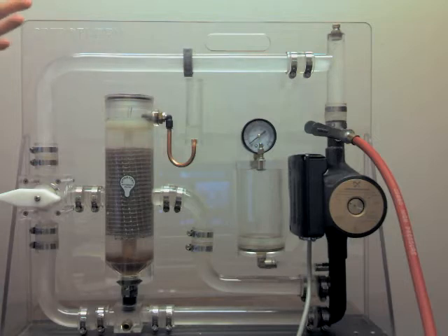What we want to show you here is that I pumped in a lot of air and this system is still circulating right now. So you may think, well, I don't really have any problems with air. My facility is heating or it's cooling fine. Nobody's complaining. The system is working. You still may have air in there, and you very likely will. It's just from an efficiency standpoint, you may not be reaching the peak system that it was designed for.